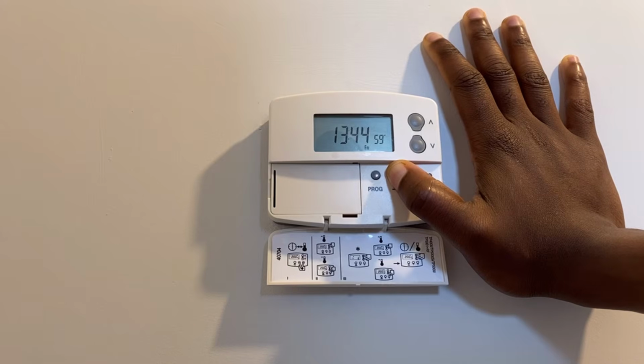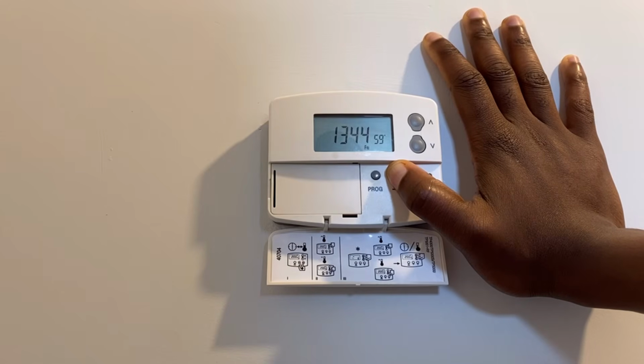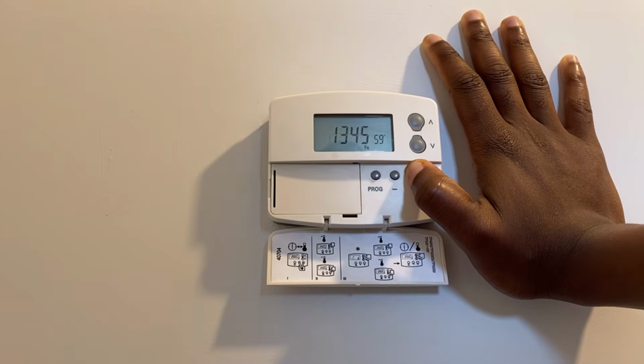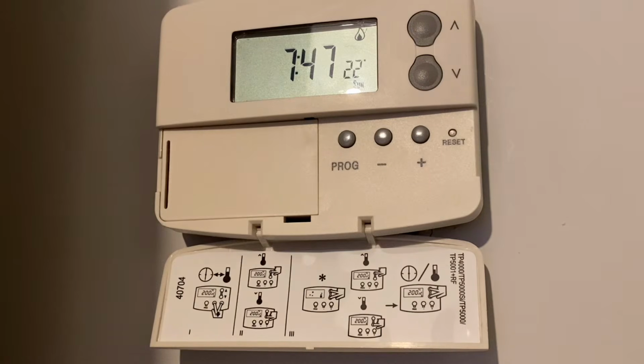For block A and block B programs, and essentially to program both the A and B program modules, you need to press and hold the program and the down button for 3 seconds, which pretty much takes you to the user advanced programming option 1. Use the up and the down keys to enable or disable the function, 0 or 1. And subsequently use the plus or minus button and the up and down button to adjust your thermostat's feature, but I'm only sparingly covering this here. I will cover it in depth in a subsequent video, and that's about it really.